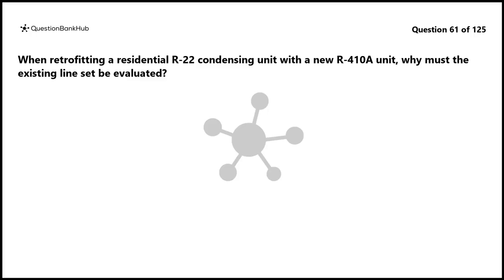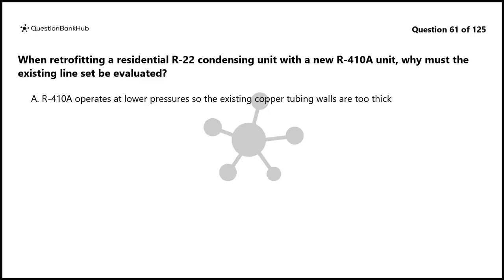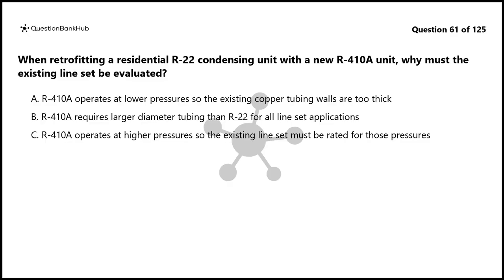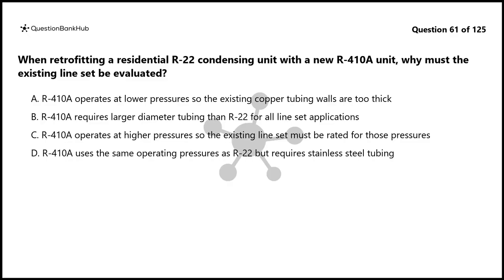Question 61. When retrofitting a residential R22 condensing unit with a new R410A unit, why must the existing line set be evaluated? A. R410A operates at lower pressures so the existing copper tubing walls are too thick. B. R410A requires larger diameter tubing than R22 for all line set applications. C. R410A operates at higher pressures so the existing line set must be rated for those pressures. D. R410A uses the same operating pressures as R22 but requires stainless steel tubing.